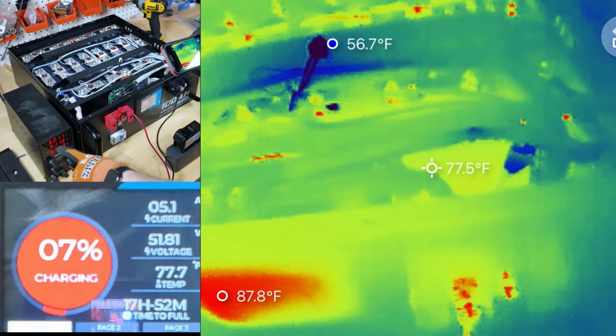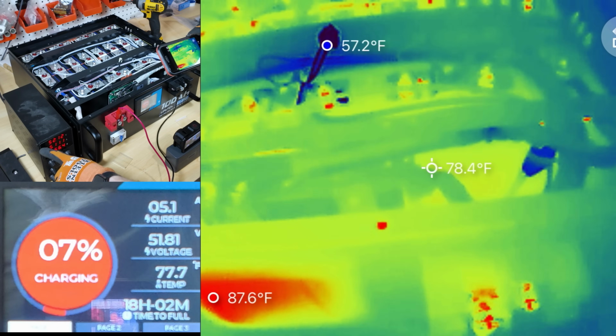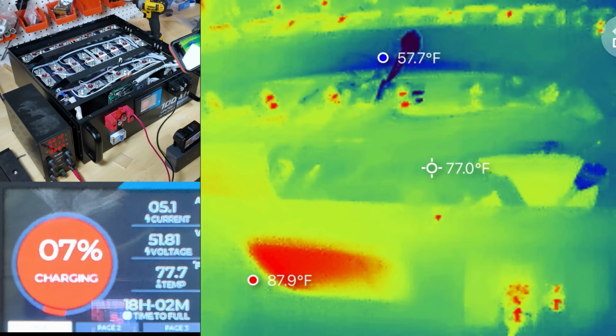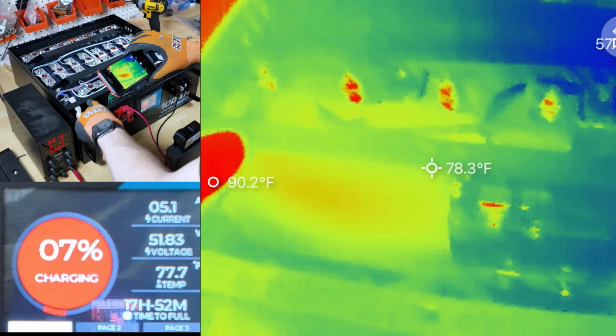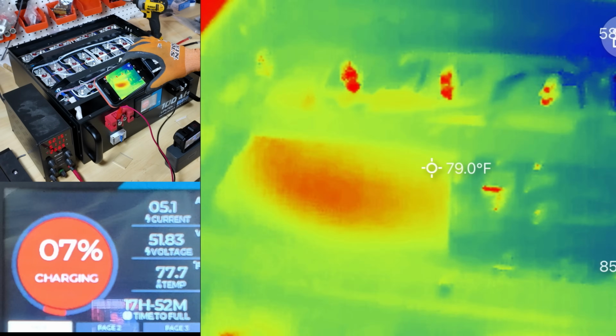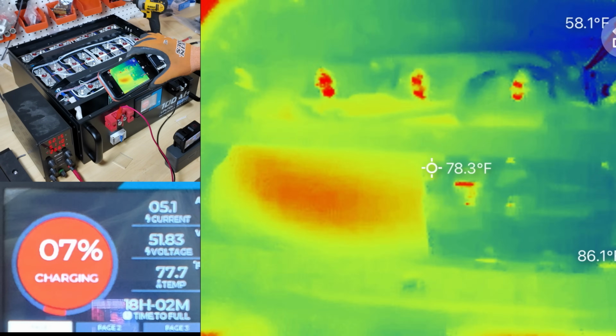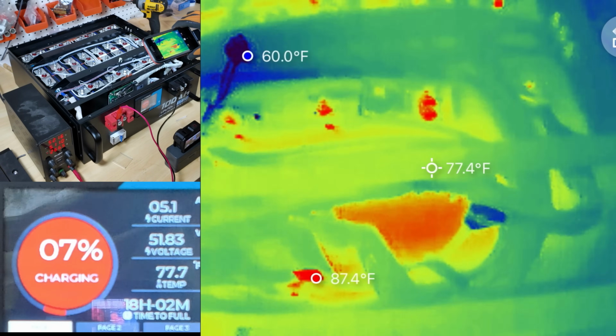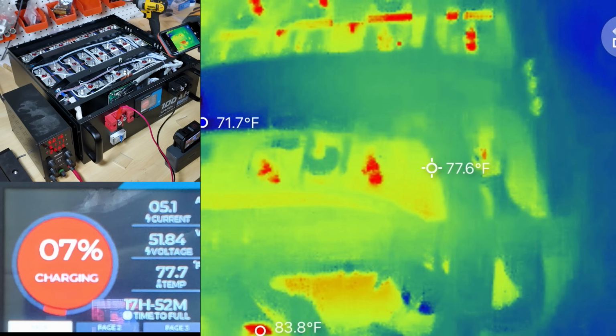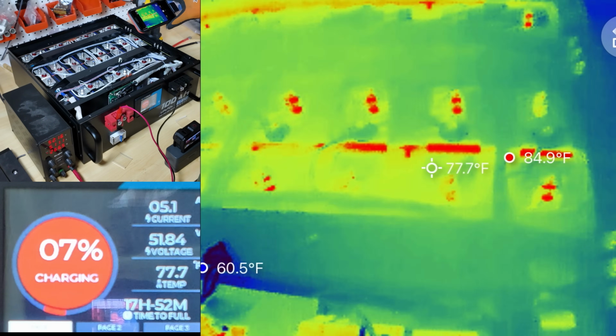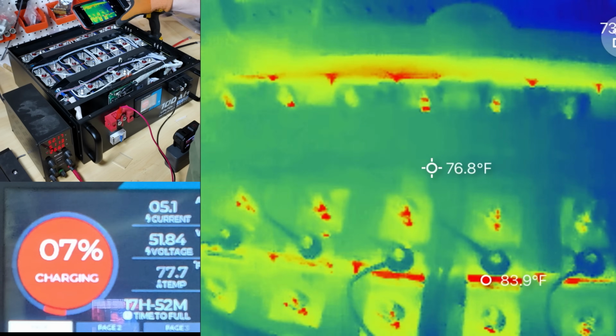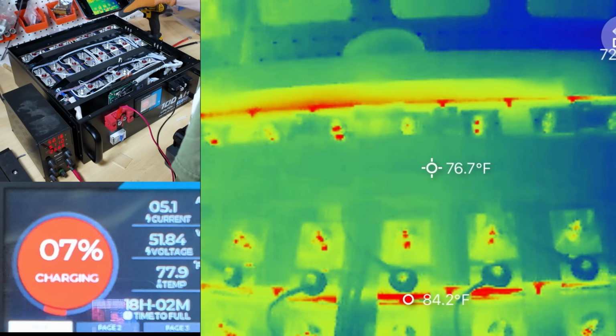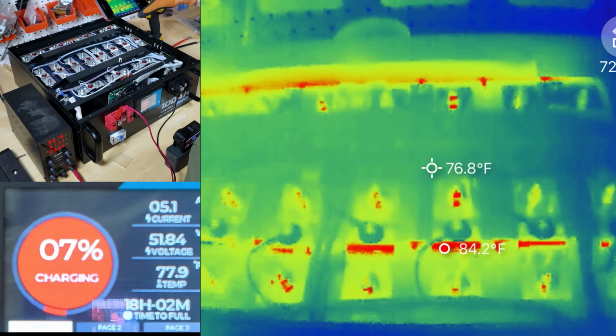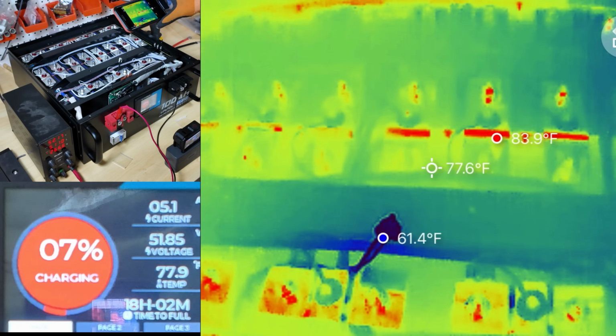So now we've got a full 5 amps coming off the charger going into the battery bank. You can see that orange area, that's from the plate warming up from the heater. Oh, there it is down there too. Very cool. You should get even heat distribution, and with about 4.5 amps going straight to those heaters, they warm up pretty quickly.